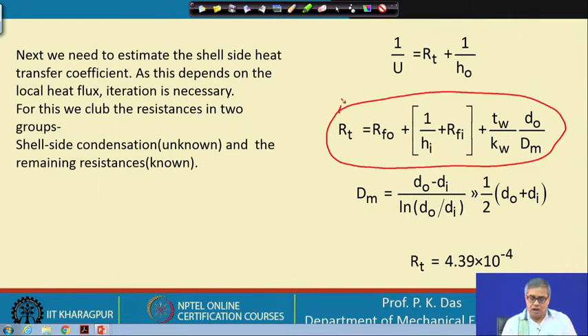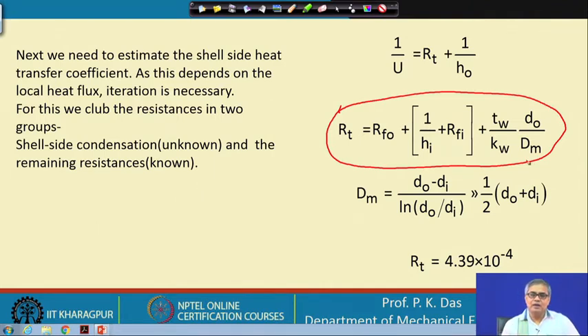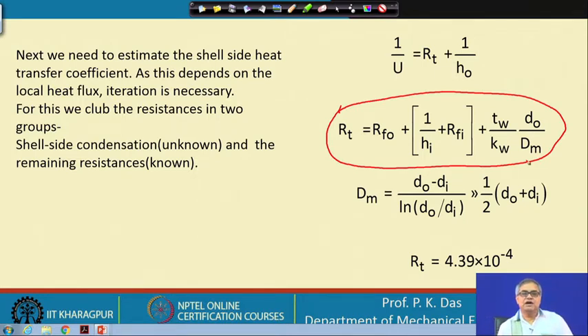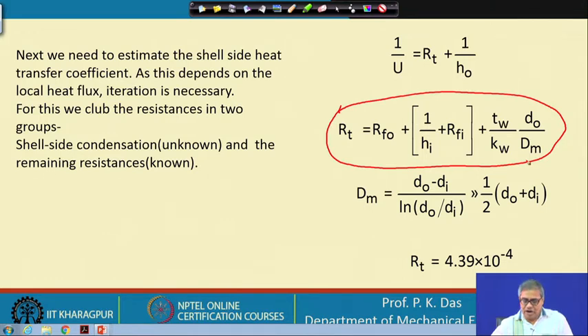The overall heat transfer coefficient combines one resistance grouping for all known resistances and another for the condensing resistance on the tube. R_T is given by a formula that includes: outside fouling resistance, the coolant-side convective resistance, the tube-side fouling resistance, and the tube wall conduction resistance. For the conduction resistance, we use a mean diameter as an approximation rather than the full logarithmic relationship.